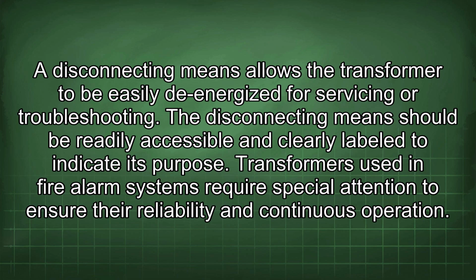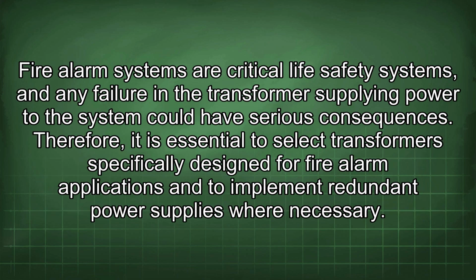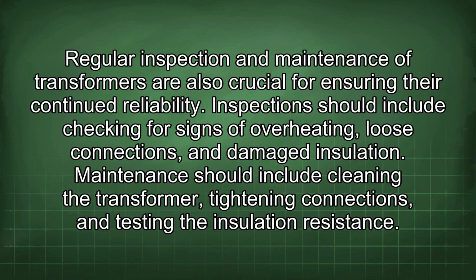Transformers used in fire alarm systems require special attention to ensure their reliability and continuous operation. Fire alarm systems are critical life safety systems, and any failure in the transformer supplying power to the system could have serious consequences. Therefore, it is essential to select transformers specifically designed for fire alarm applications and to implement redundant power supplies where necessary. Regular inspection and maintenance of transformers are also crucial for ensuring their continued reliability. Inspections should include checking for signs of overheating, loose connections, and damaged insulation. Maintenance should include cleaning the transformer, tightening connections, and testing the insulation resistance.